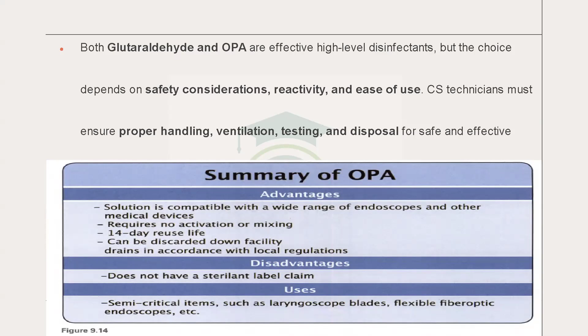Does not have a sterilant label claim. Unlike the glutaraldehyde that can lead to sterilization after 10 hours soak time, the OPA has no sterilization claim. It has no sterilization claim. That is the downside of it, and it's used for semi-critical. Now, next slide, please.